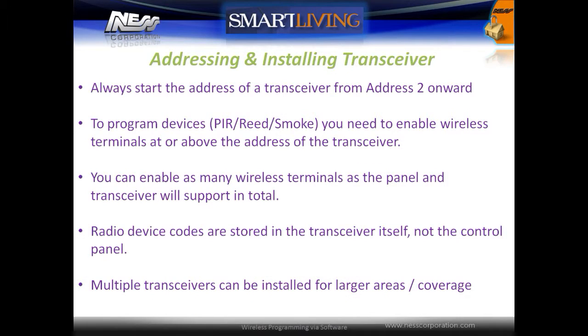When installing and addressing radio transceivers, always start the address of a transceiver from address 2 onwards. To program devices such as PIRs, reed switches and smoke detectors, you need to enable wireless terminals at or above the address of the transceiver. Radio device codes are stored in the transceiver itself, not in the control panel. It is possible to install multiple transceivers for large area coverage.